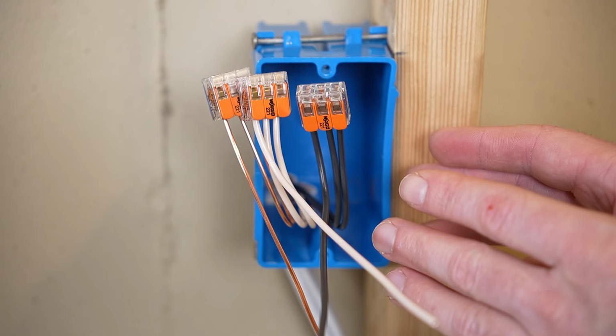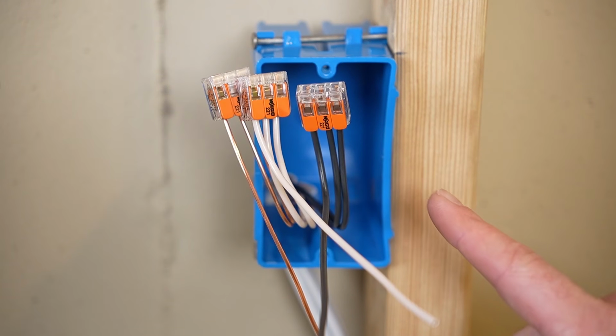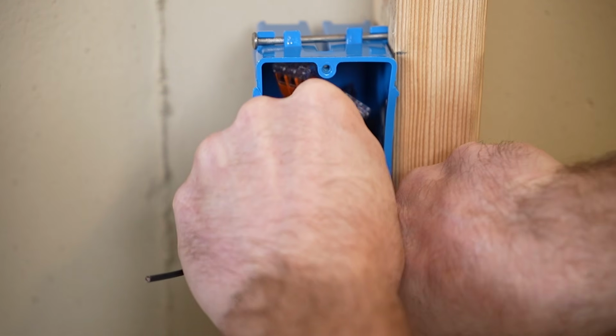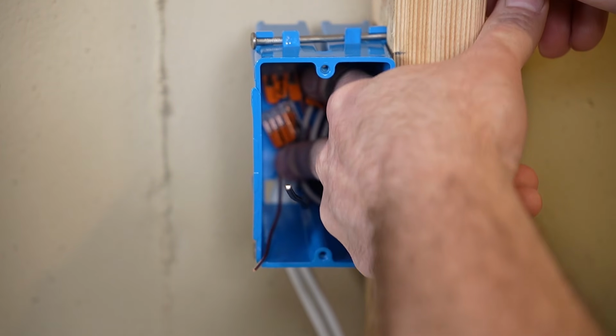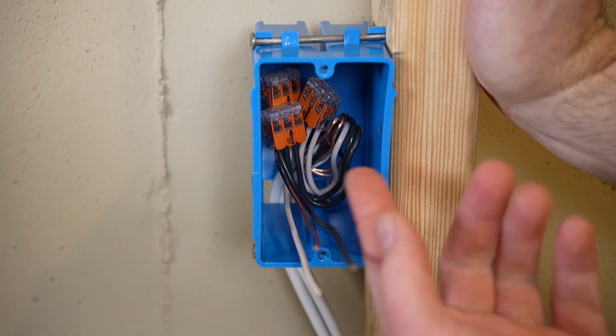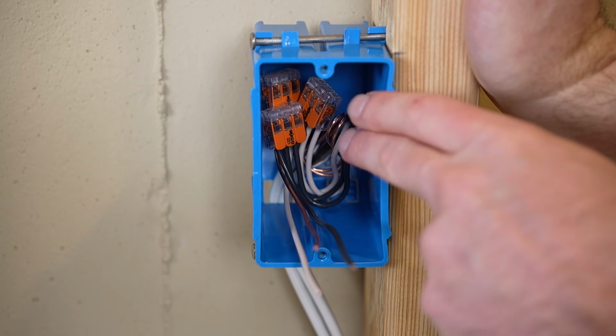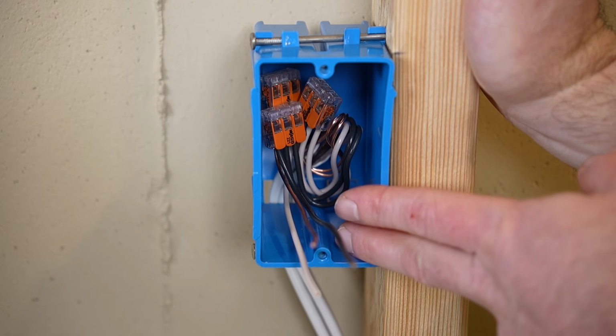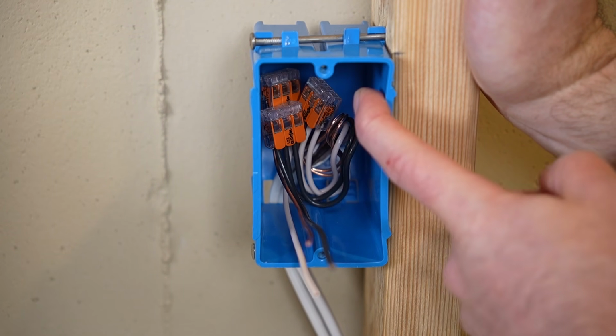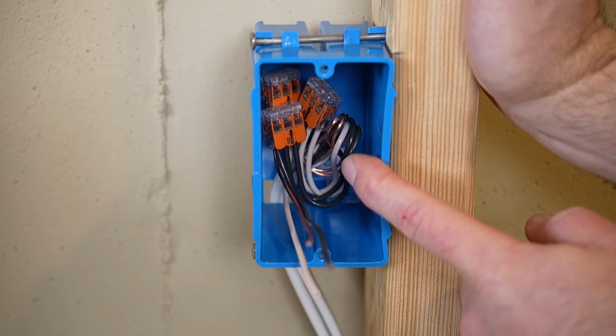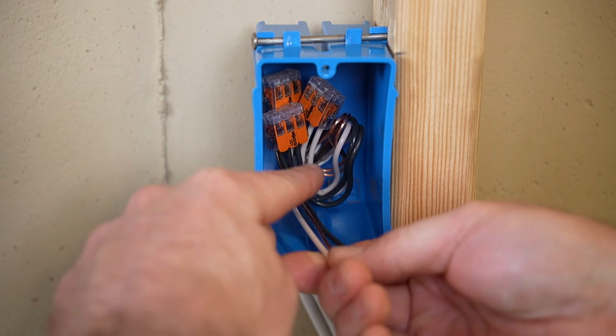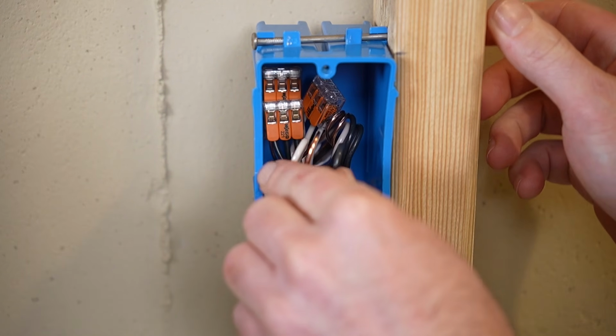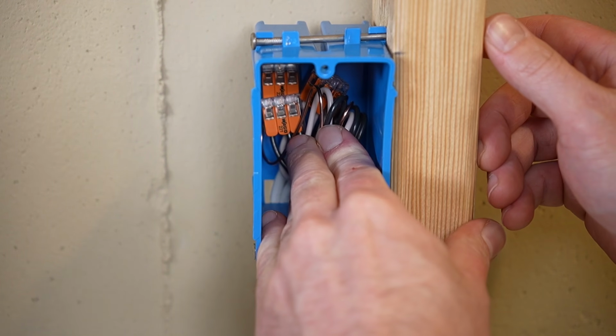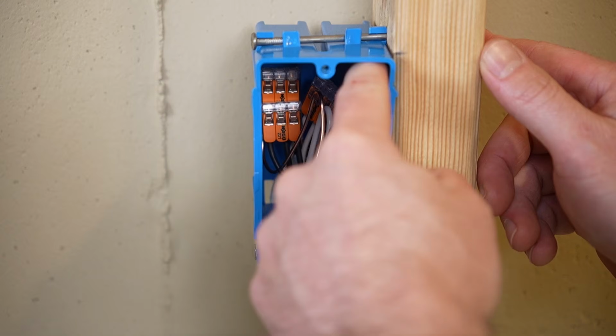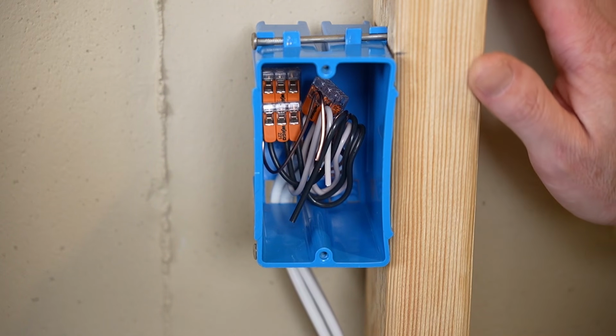Now same thing like we just did with the Wirenuts, we have to fold all these wires into the back of the box to get ready for the rough-in phase. Just like with the Wirenuts, these Wagos should be hats, not buckets. We want stuff that's going to fall down into them to shed off and not get caught up inside the connection. So we're going to want to make sure these things are facing up. And then with our pigtails, we're going to want to loop them towards the front and then shove them all in the back so they don't get caught with the roto-zip when they cut the sheetrock open.